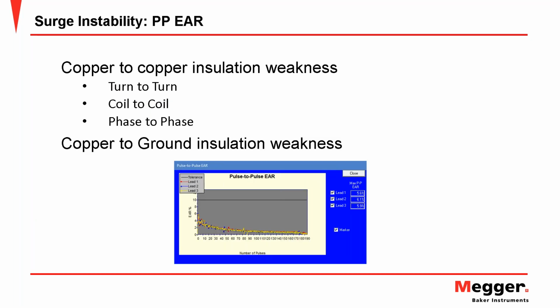Okay, so finally, surge testing. I've talked about that turn-to-turn, copper-to-copper, phase-to-phase relationship earlier, but that no other testing is going to evaluate. So it's super critical because according to some studies, 80% of winding failures begin first as a copper-to-copper insulation failure. Then once the copper-to-copper touches off and it fuses, it's going to have an internal effect we call the autotransformer effect, which causes the motor to exhibit a lot of internal circulating currents, which go undetected by your protection circuit, that causes your winding to burn up. And I'll show you a picture of that here in a second.